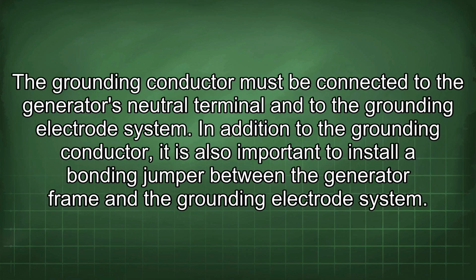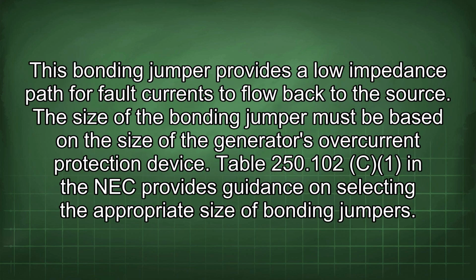The grounding conductor must be connected to the generator's neutral terminal and to the grounding electrode system. In addition to the grounding conductor, it is also important to install a bonding jumper between the generator frame and the grounding electrode system. This bonding jumper provides a lower impedance path for fault currents to flow back to the source. The size of the bonding jumper must be based on the size of the generator's overcurrent protection device.